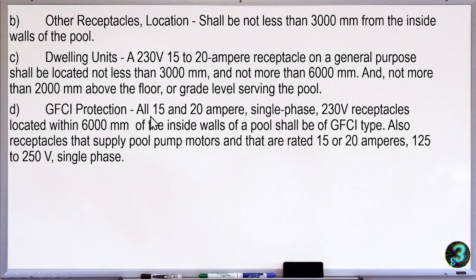Ang GFCI, so protection for the pools, all 15 and 20 ampere, single phase, 230 volts receptacle located within 6,000 mm pala, or of the inside wall of a pool shall be GFCI type. Also, receptacles that supply pool pump and that are rated 15 to 20 amperes, 125 to 250 single phase shall be also protected by a GFCI.